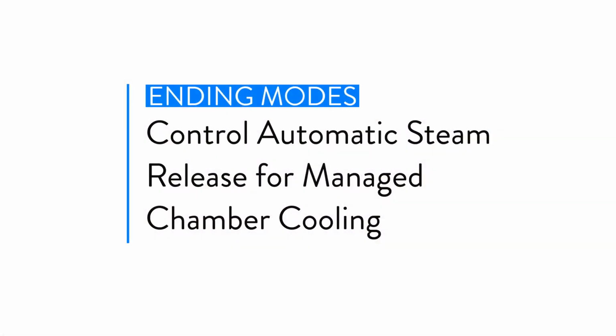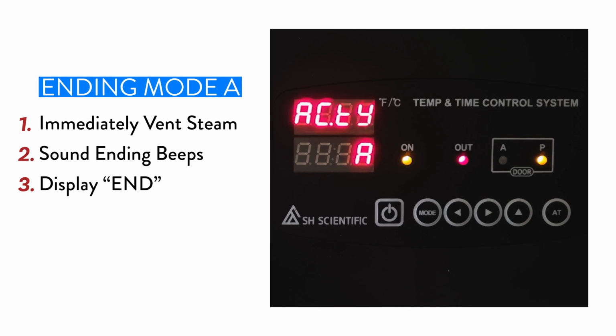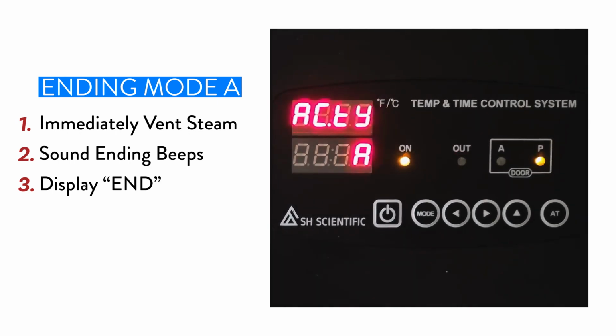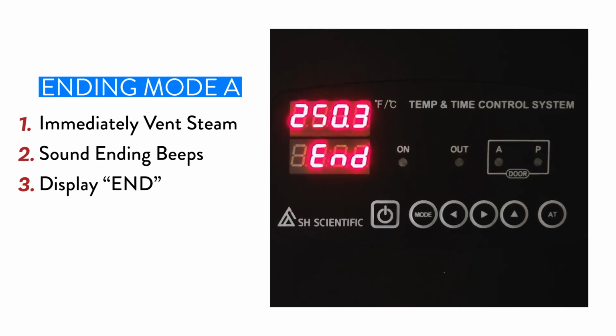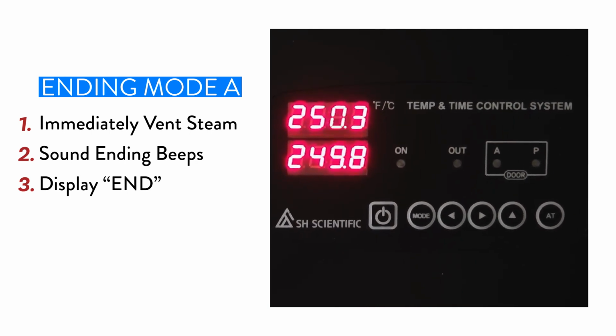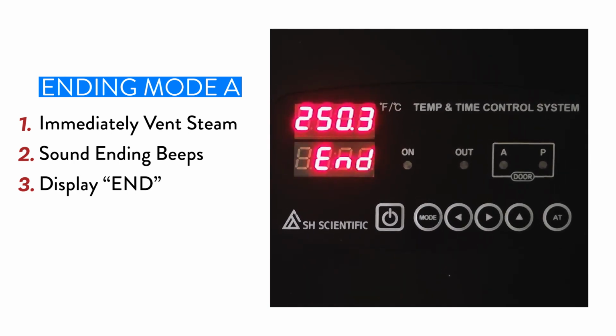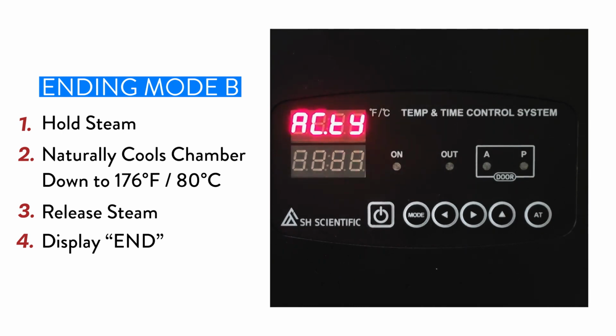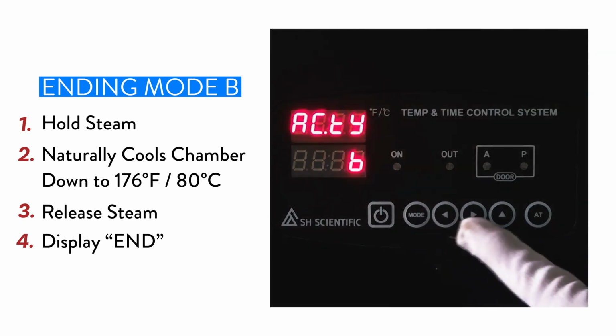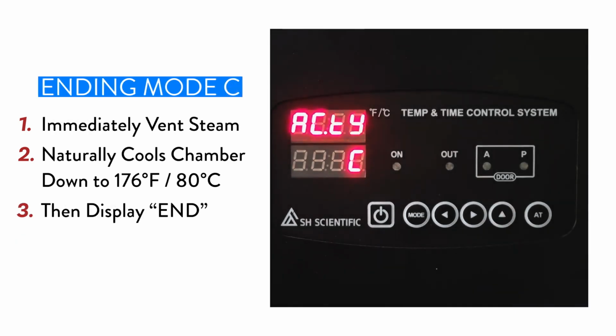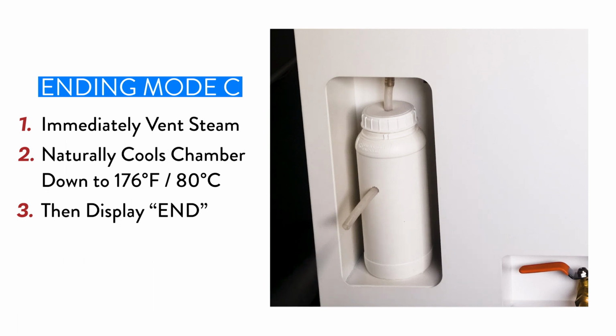Now, let's take a closer look at what ending modes A, B, and C will do at the end of the sterilization time. Ending mode A will immediately vent the steam, sound a beep, and display end. This is a nice setting for glassware, for instance. Ending mode B will hold the steam until the chamber has cooled naturally to 176 Fahrenheit or 80 Celsius. At that point, it will vent the steam and display end. This mode is nice for sterilizing polypropylene grain bags. Ending mode C will immediately vent the steam, but will not display end until the chamber has cooled naturally to 176 degrees Fahrenheit or 80 Celsius.